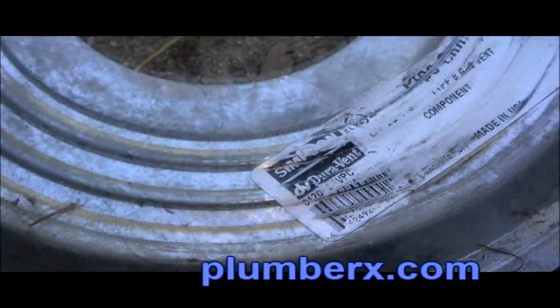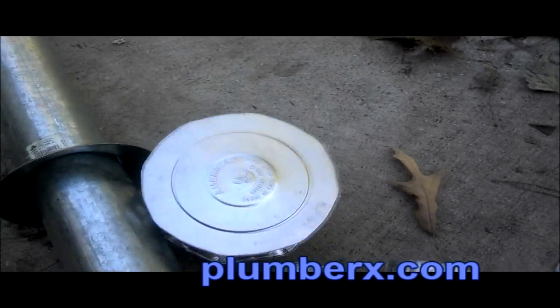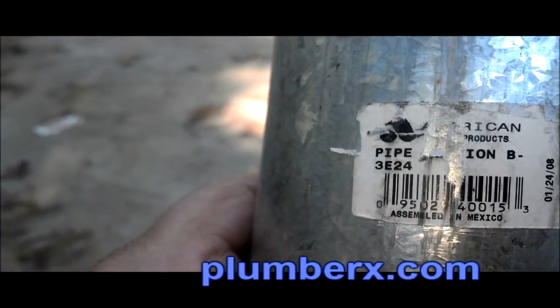This here is going to be the heat shield, made by DuraVent, but it will adapt to AmeriVent. When you go to purchase 3-inch flue pipe, it's important to know there are two different brands and they do not match up with one another. You have AmeriVent and you have DuraVent — both are 3-inch double wall flue pipe, but they will not connect to each other. So if you're trying to tie on to the existing flue pipe you have, make sure you get the one from the same manufacturer.